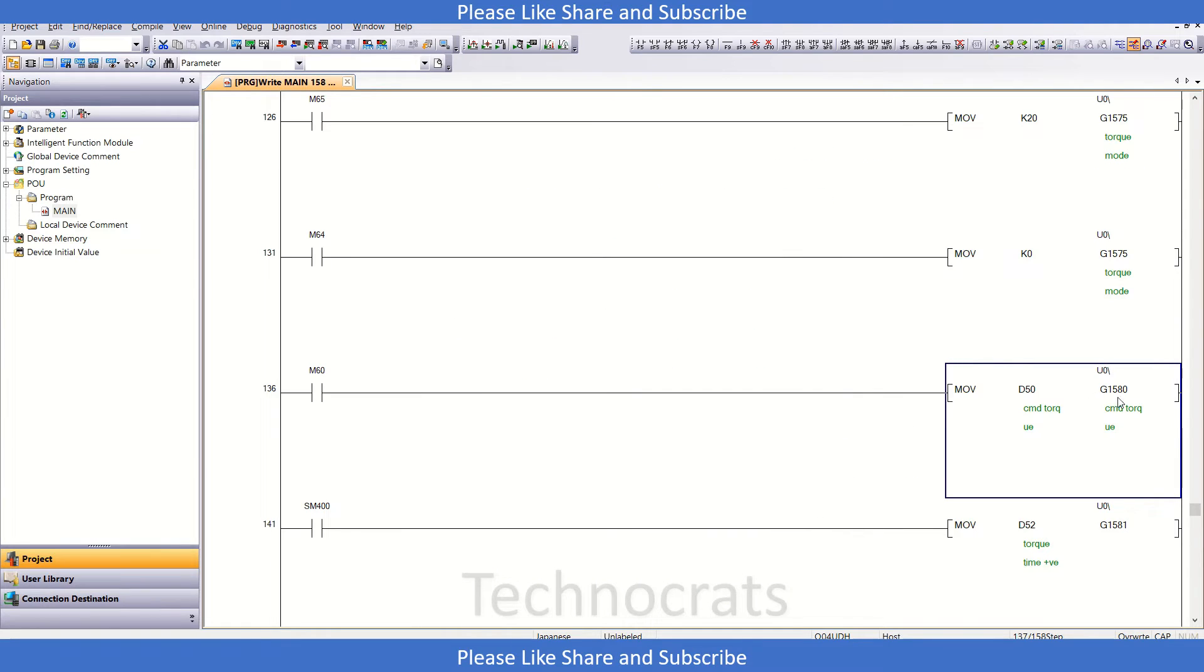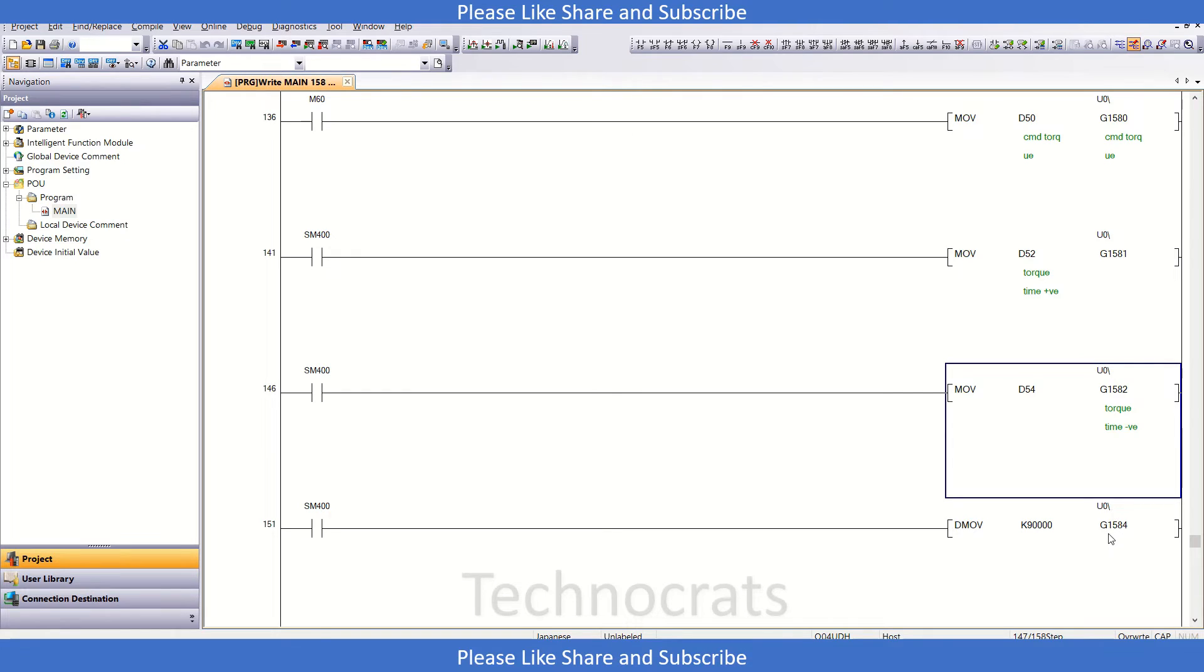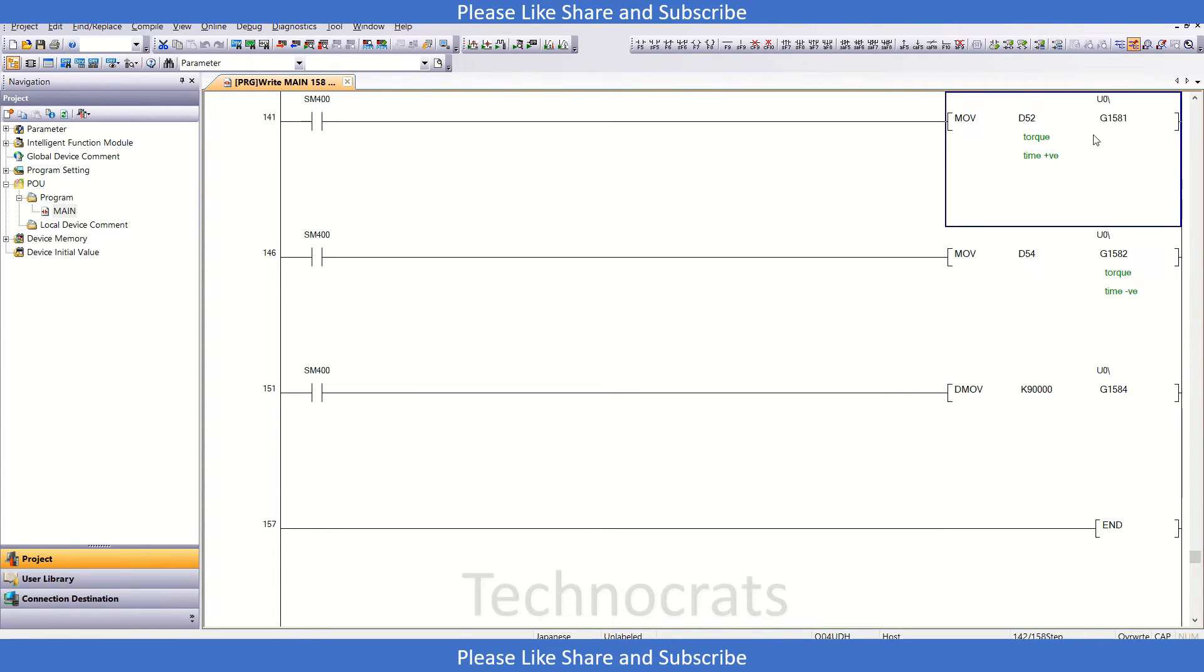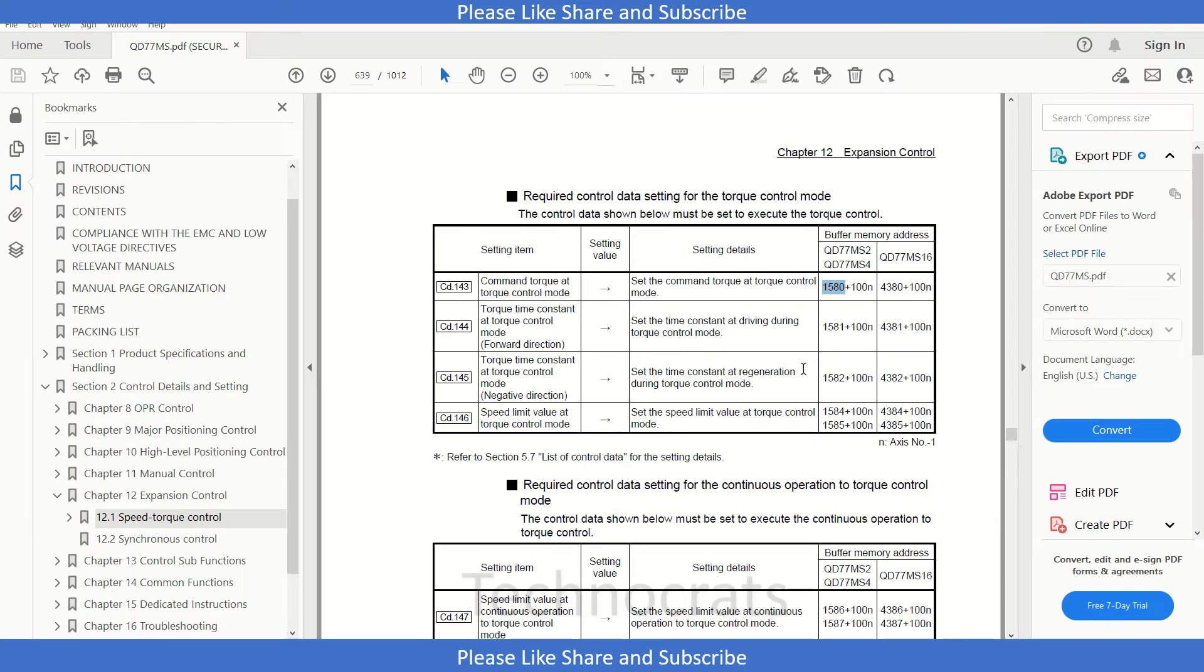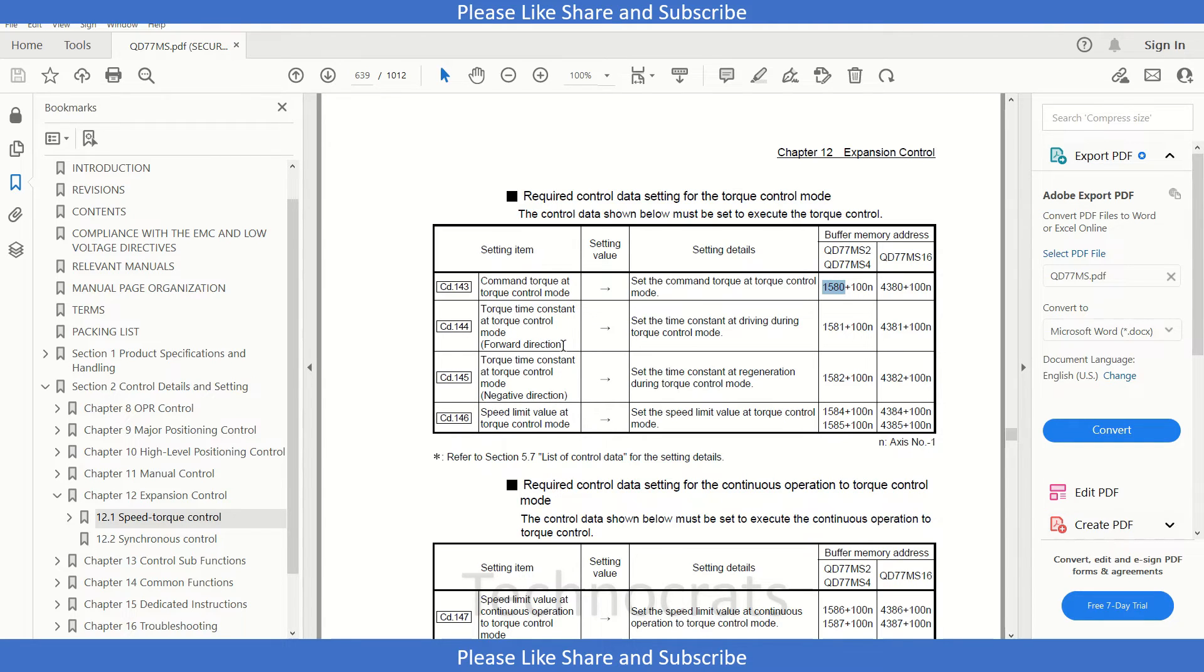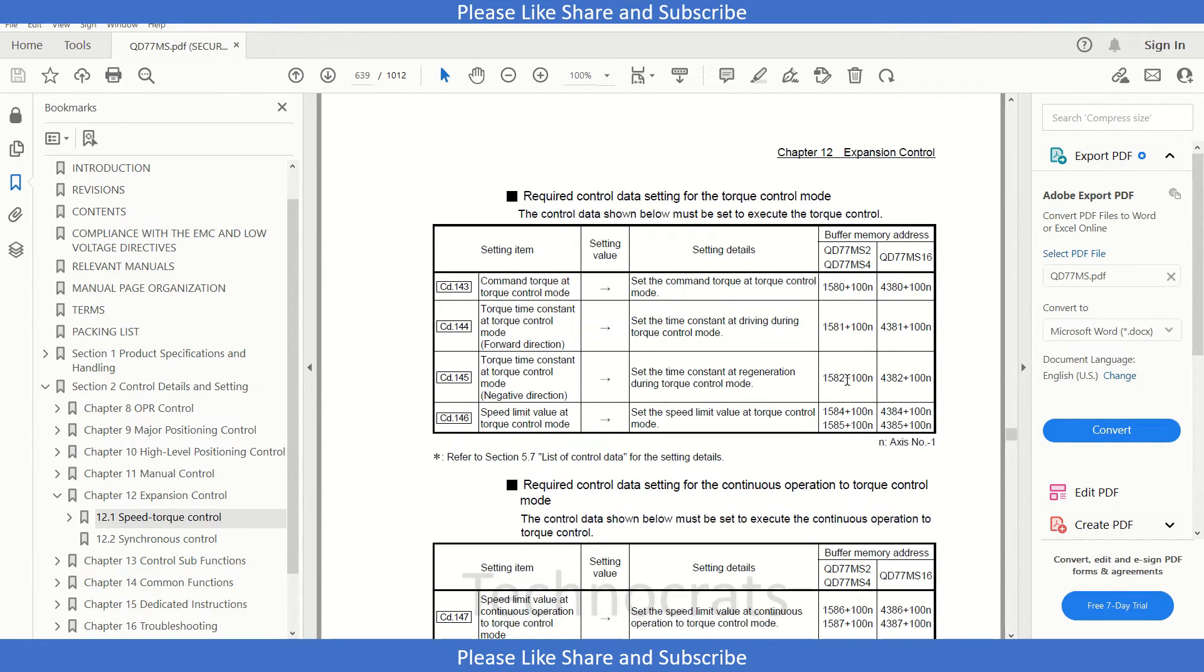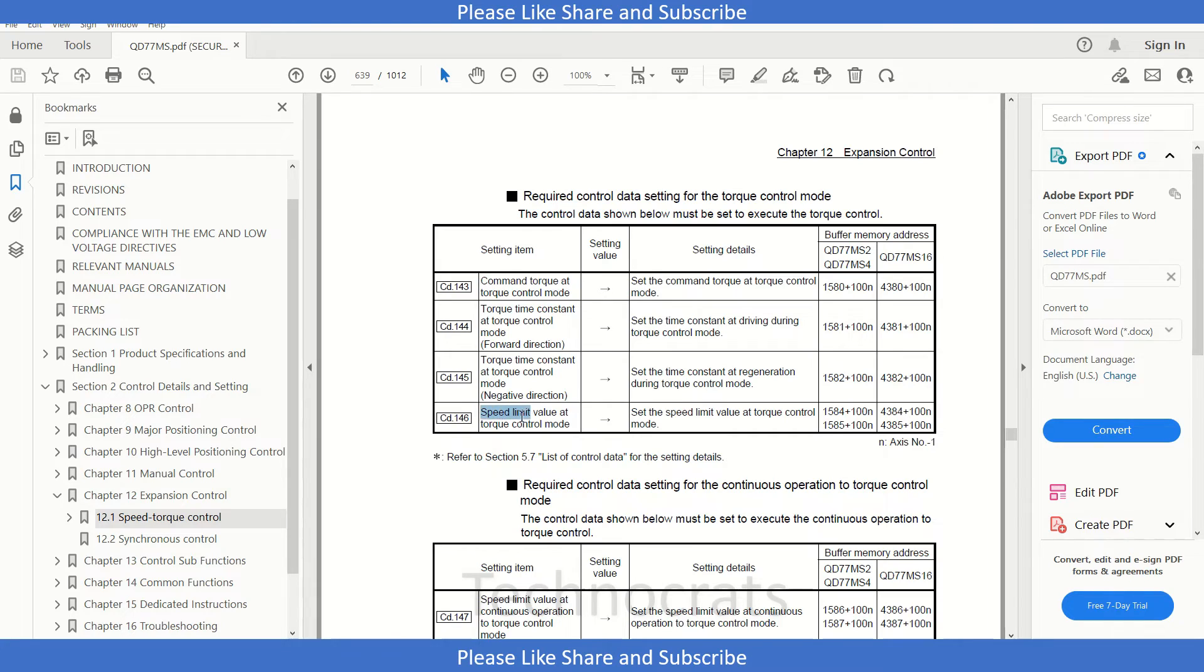Then we have 1581, 1582, and 1584. So 1581 - let me show you in the manual - 1581 is torque time constant at torque control mode for positive direction. 1582 is for torque time constant at torque control mode negative direction. And this is the speed limit for torque control mode, that is in 1584, and it is a double register.